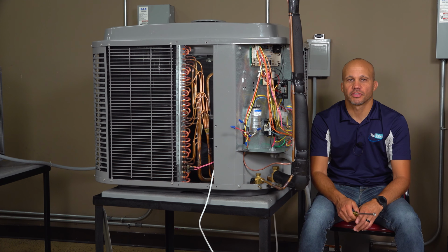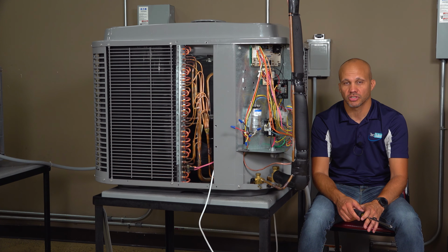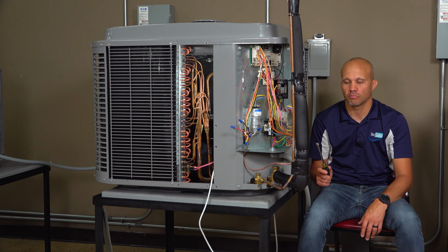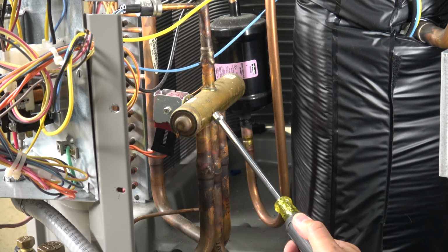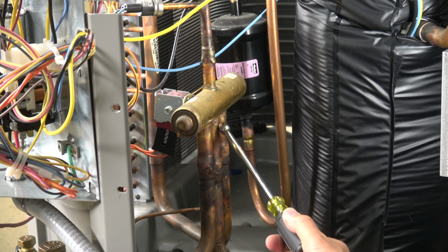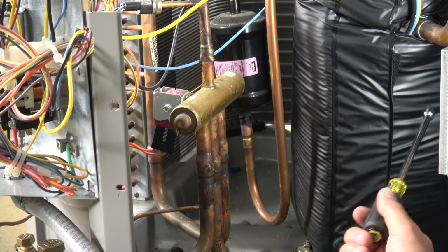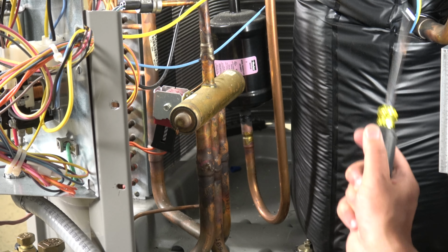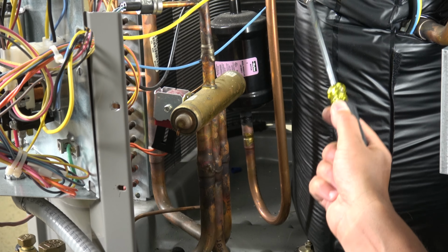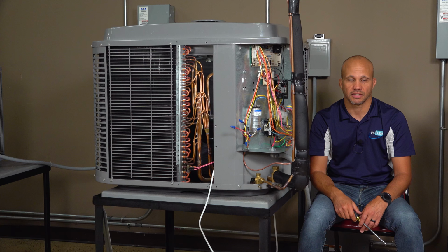So we got a few of the panels off of this unit so we can see the inside of a heat pump and the main component that is different, which is the reversing valve. This is what allows us to switch from heating to cooling mode. So let's pretend we're in cooling mode right now. The refrigerant comes in from the indoor unit. It goes into this reversing valve, which is currently positioned in the cooling mode, so it comes out this next pipe. It makes its way through the accumulator and into the compressor. The compressor compresses the refrigerant to increase its pressure, so it's hotter than the coil outside. It comes out the top of the compressor and routes its way back into the other side of the reversing valve and out to the condenser coil where it can reject its heat.